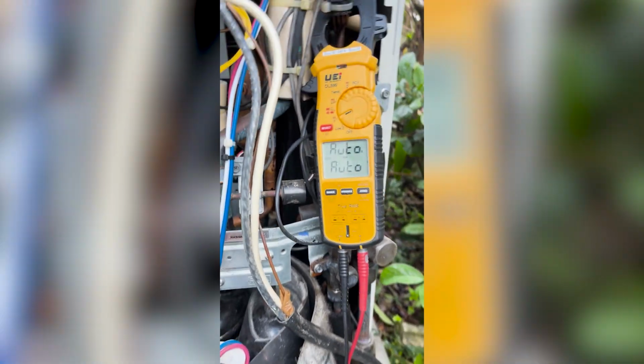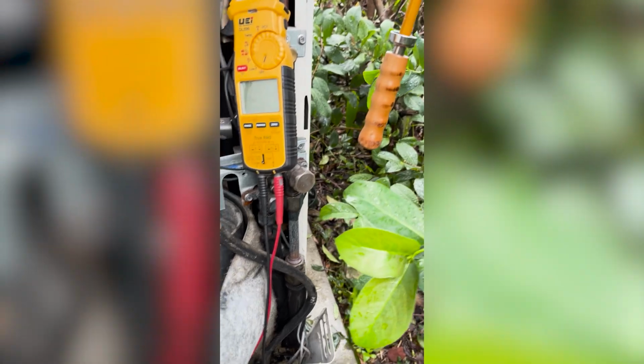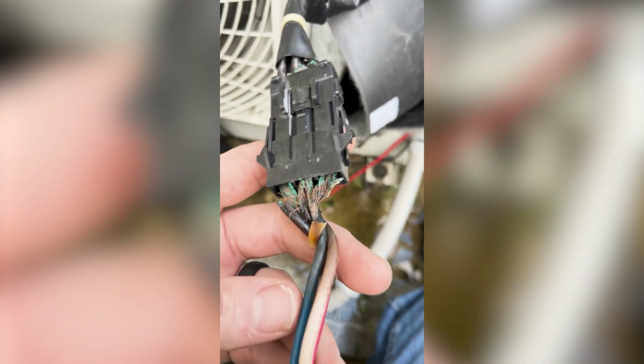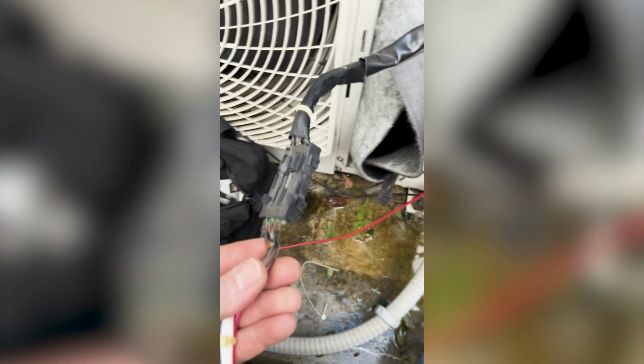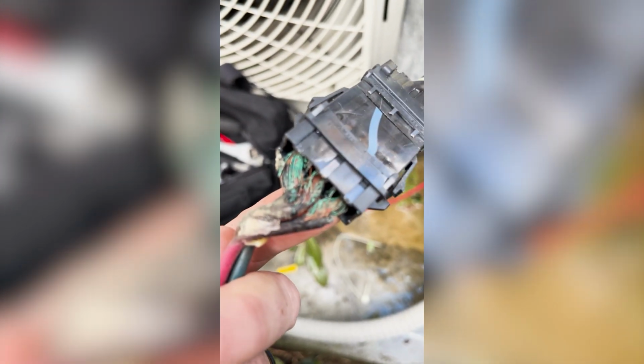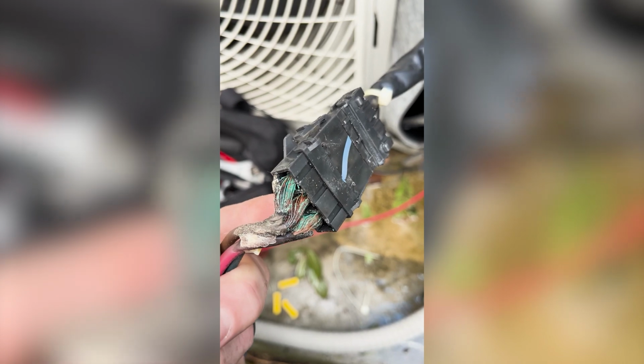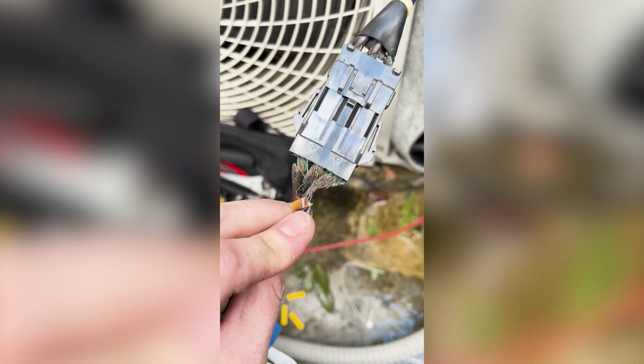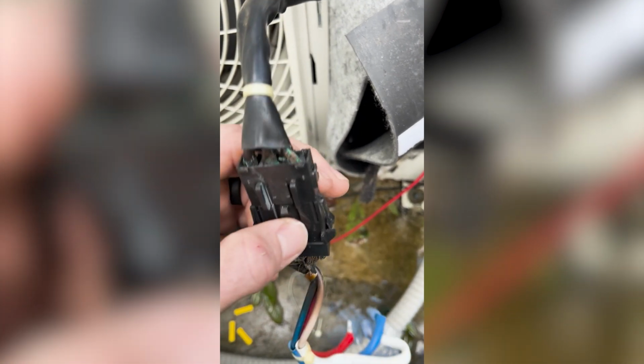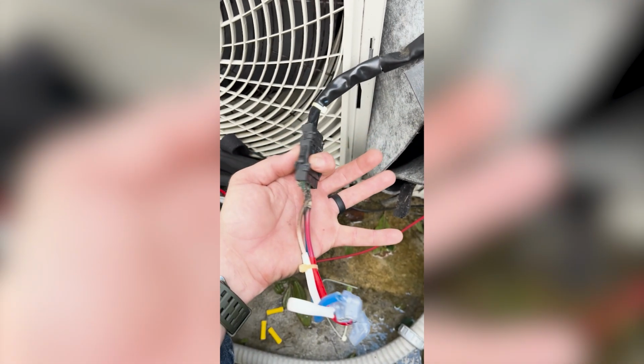All right, updates. So my system had an L5 error code. Turn that off. And wouldn't you know, the plug looked like it got a little toasty on that compressor there. A discoloration on the wire, all the wires melted together. But you see this inverter system, when it went to go start it, noticed that it was grounded out. Didn't even attempt to send voltage, so nothing is blown out. It looks like the quick disconnect plug is shot, so I'm going to do a repair on this and see if we can get it back up and running.